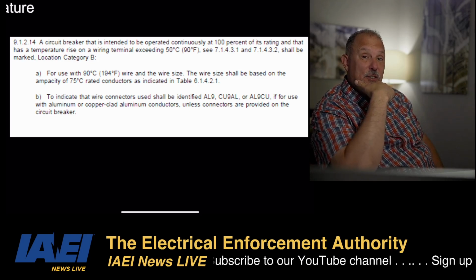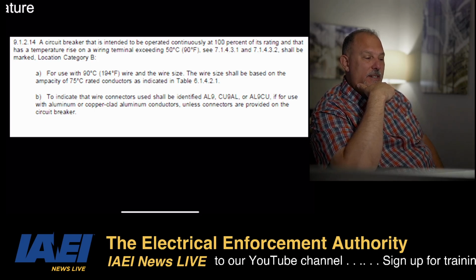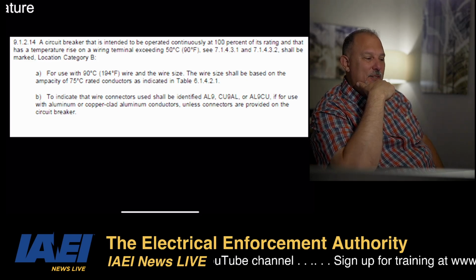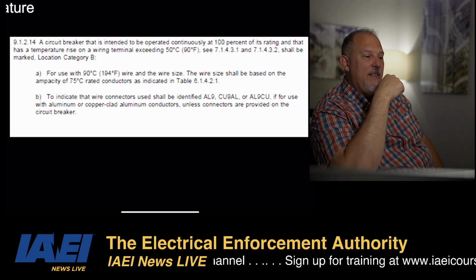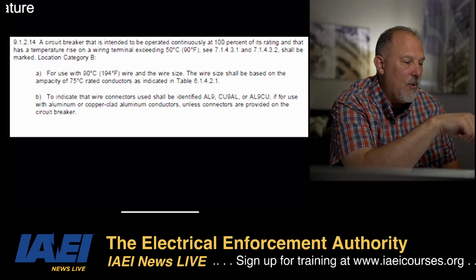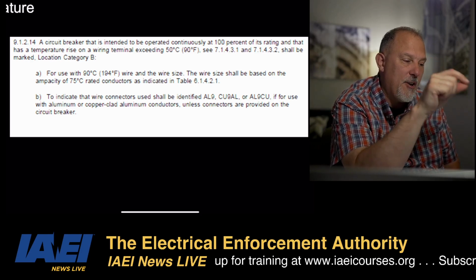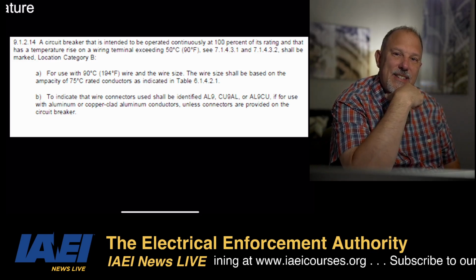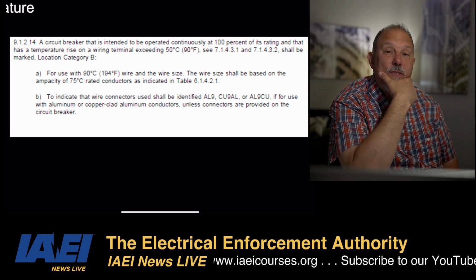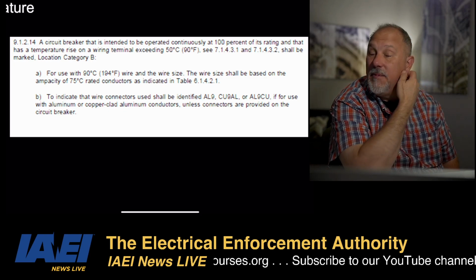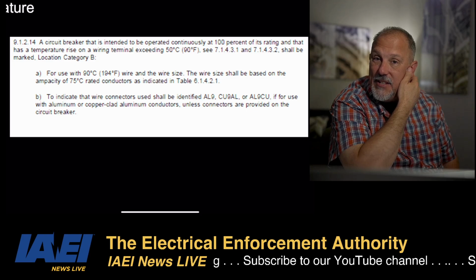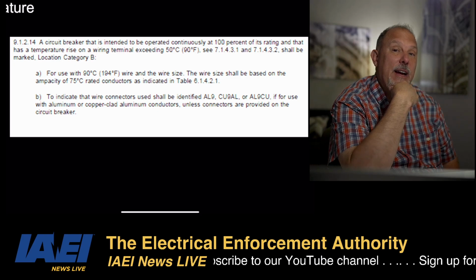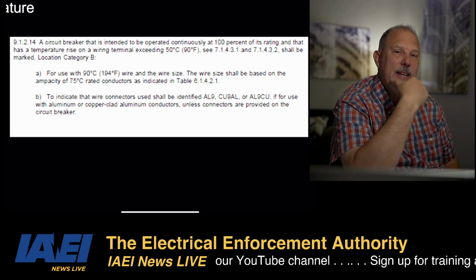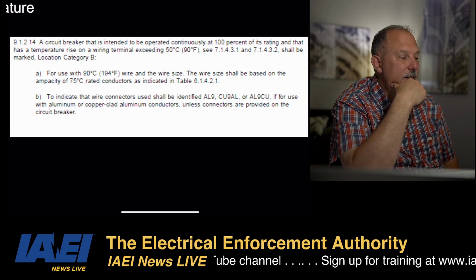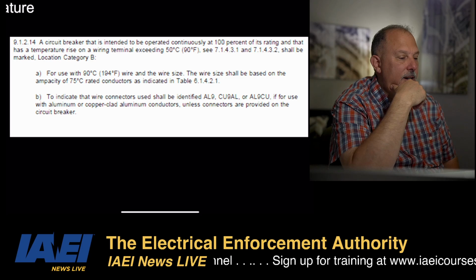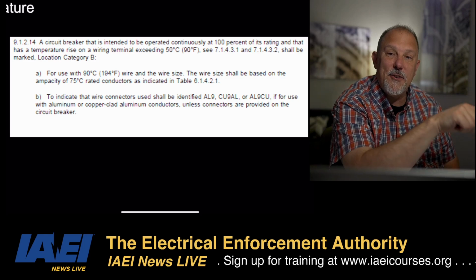So you could see a circuit breaker that says use 90 degrees C conductor at its 75 degrees C ampacity. But the reason is, or the application would be, when used at 100% of its rating. I just recently got this question, and I'm hoping I answered it correctly. Somebody pointed this out to me on a circuit breaker that they took a picture of, and it said to use 90 degree C conductor at the 75 degree C ampacity. And they said, why can't I use a 75 degree C conductor? And they could, as long as they're not operating it at 100% continuously.